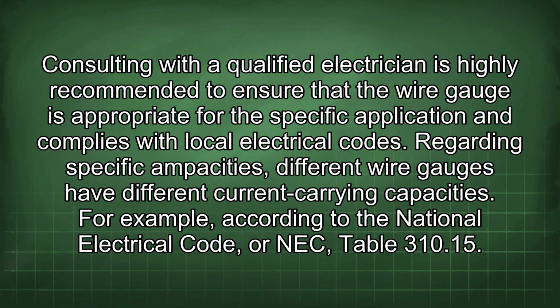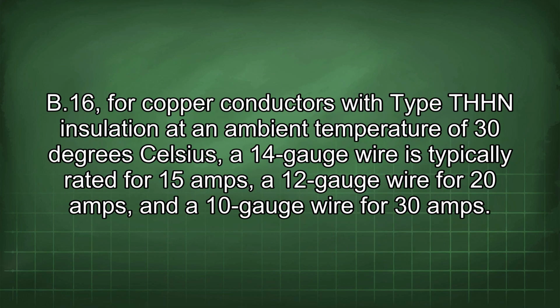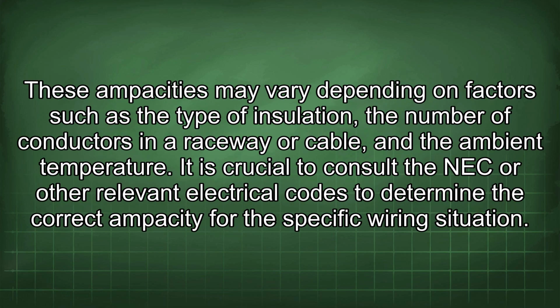Regarding specific ampacities, different wire gauges have different current carrying capacities. For example, according to the National Electrical Code, or NEC, Table 310.15(B)(16), for copper conductors with type THHN insulation at an ambient temperature of 30 degrees Celsius, a 14-gauge wire is typically rated for 15 amps, a 12-gauge wire for 20 amps, and a 10-gauge wire for 30 amps. These ampacities may vary depending on factors such as the type of insulation, the number of conductors in a raceway or cable, and the ambient temperature. It is crucial to consult the NEC or other relevant electrical codes to determine the correct ampacity for the specific wiring situation.